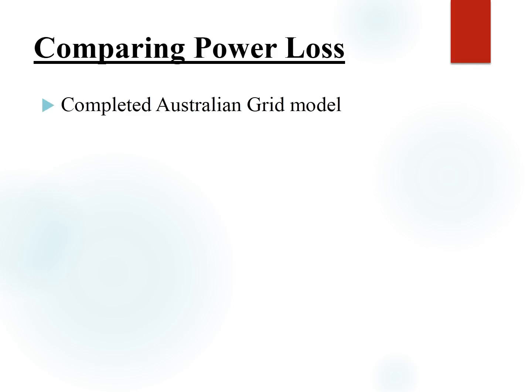For determining the power loss, at first we completed the reduced Australian grid model in PSSE34 software and saved the network data case and design in .sav and .sld files. Then we ran the load flow and obtained the total real and reactive power generation by the existing system.